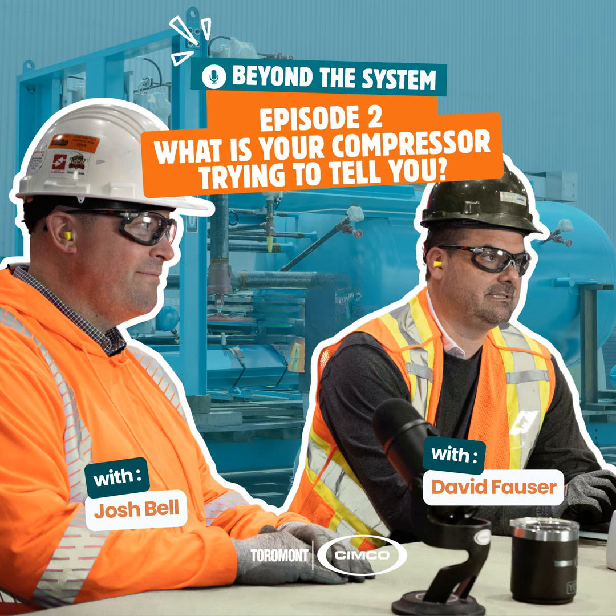In an ice rink running all year round, the best time to do maintenance, although a lot of people might not agree, is right in the heart of the season, when it's minus 25 outside, or just cooler. It takes the stress off the equipment. Maybe you have 3 compressors but only need 1, so you don't have to worry about anything, and you have time to take it down during the season.